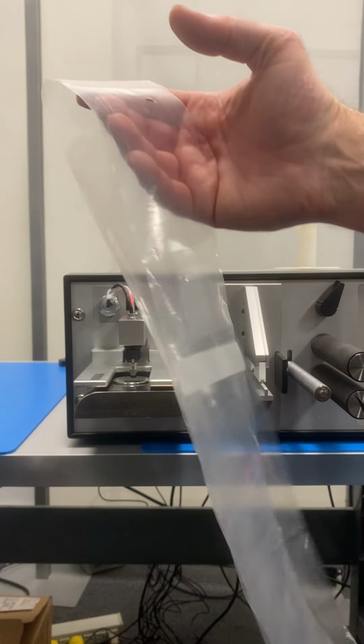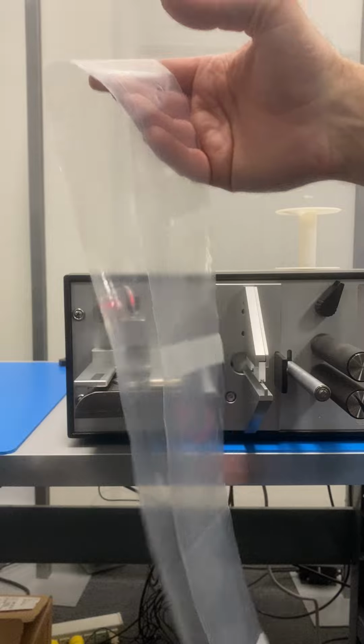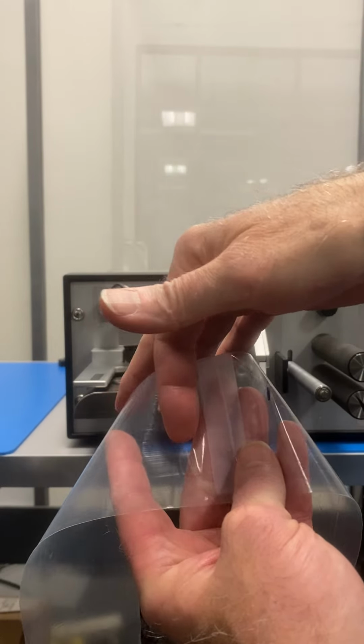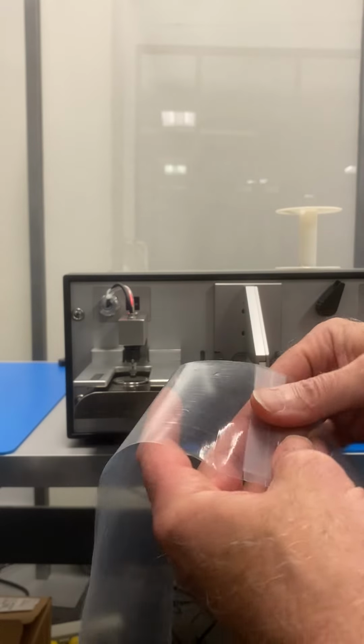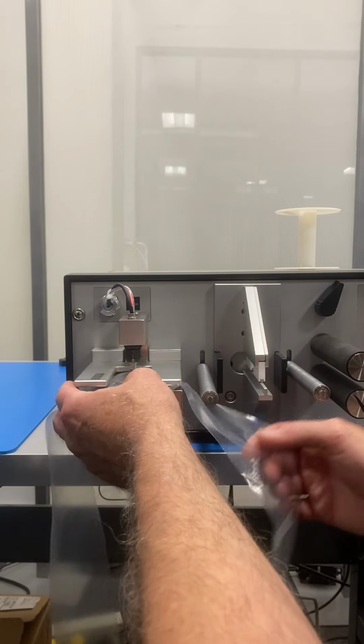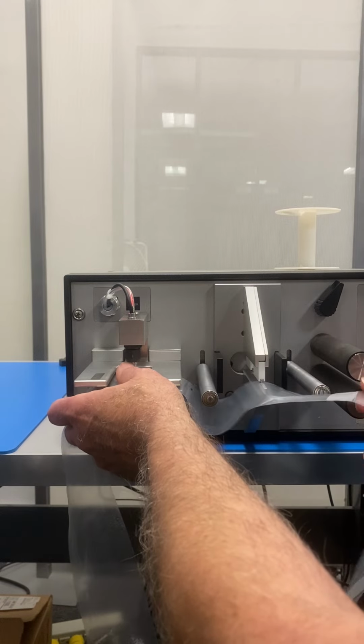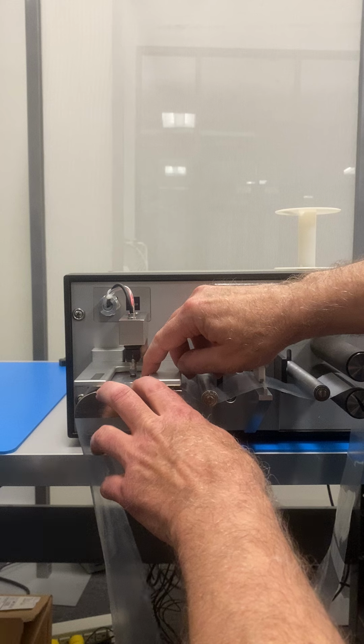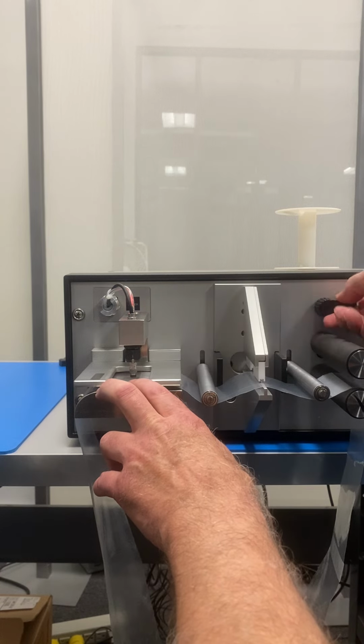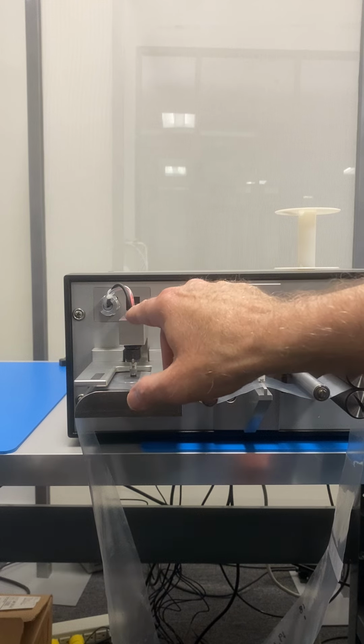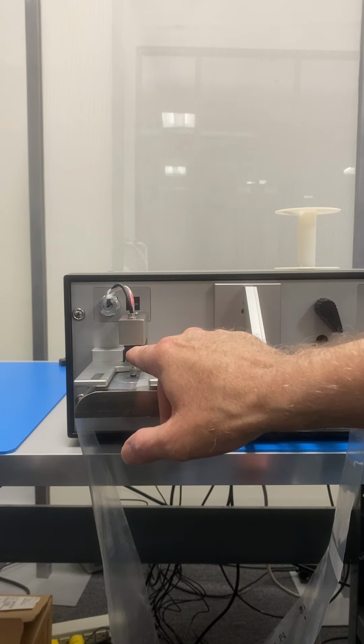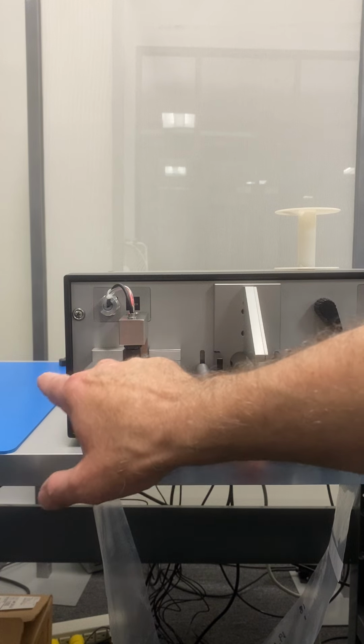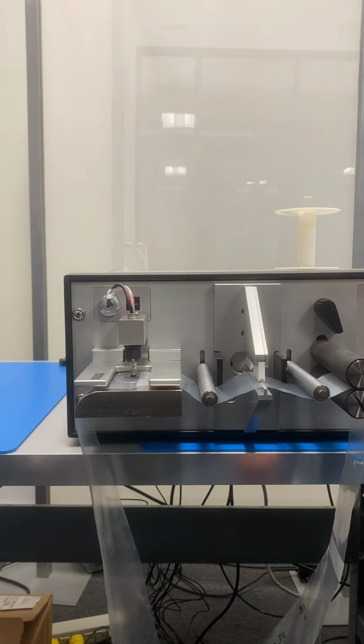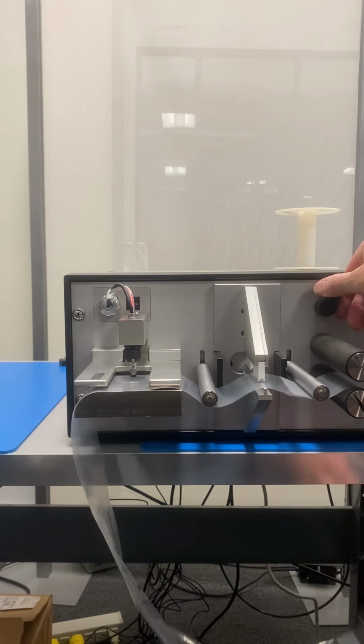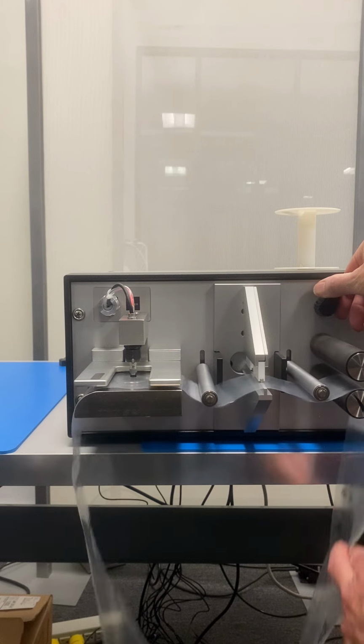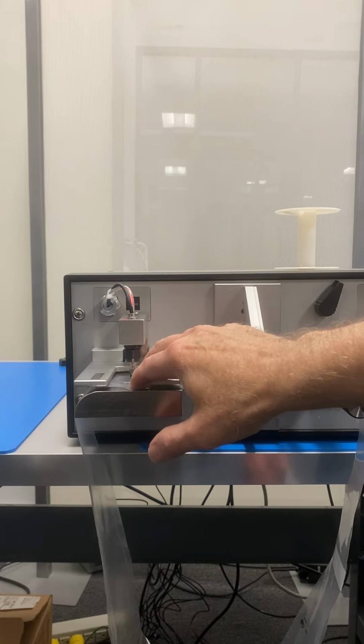When preparing a sample to run that way, there's really two methods that you could use. One would be if the sample is long enough to tape into a tube, and let's say this was your starting point and your end point was back here, you could load a tube into the system such that your starting point was just downstream of the contact sensor, and you could run it point to point. The sensor would go down, take the first point, you set the spacing and the speed, how far you want it to advance, take the second point, third, all the way around until your sample has moved back to the starting point again.